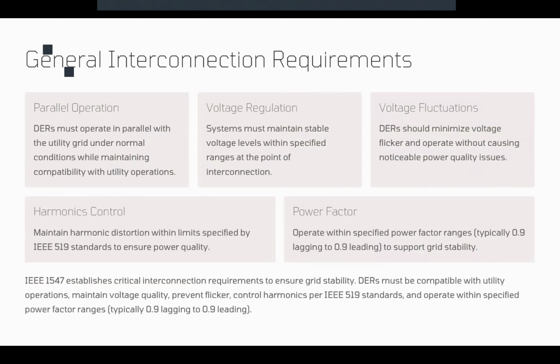Now, let's go through the general requirements for interconnection. We mentioned some of them. We wanted to repeat those to make sure we are good to go. Okay, we know everything. One is parallel operation. We said the DER should operate in parallel with the utility grid under normal conditions. Another one is voltage regulation. So they should maintain a stable voltage level. There is a specified range, okay, and they should remain in that range.